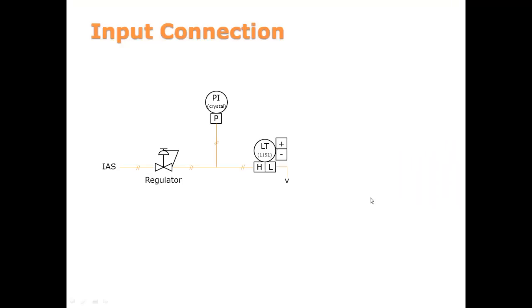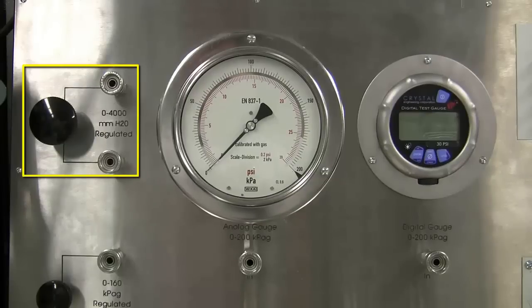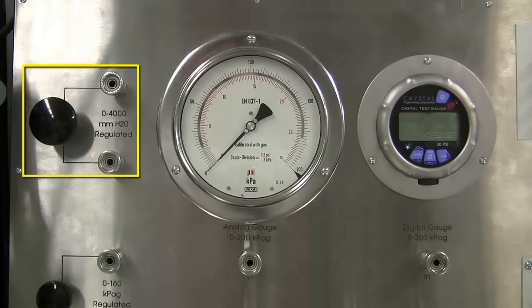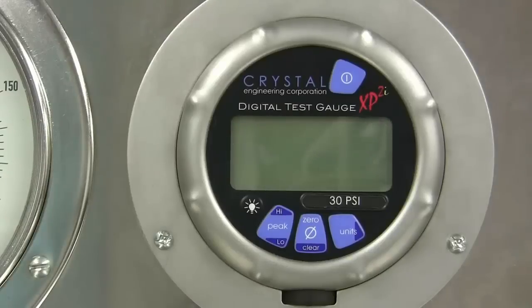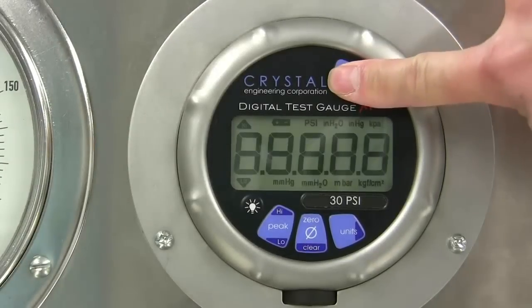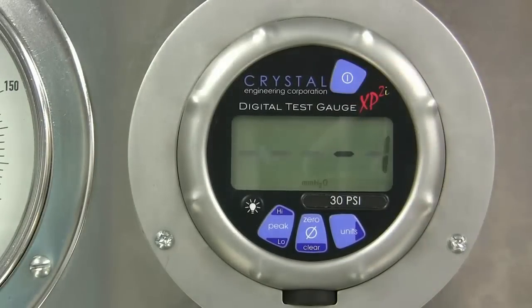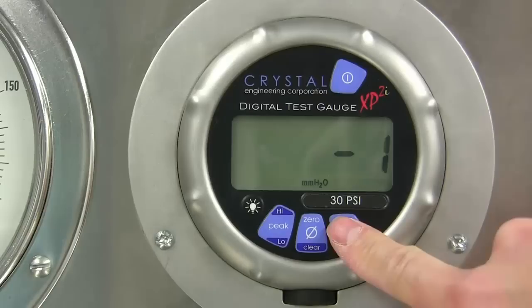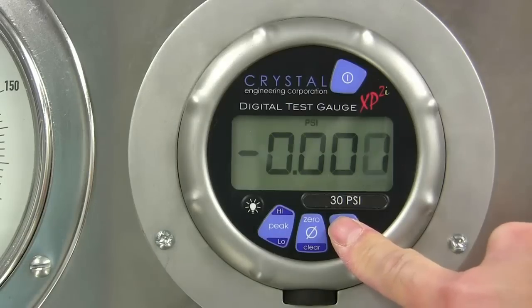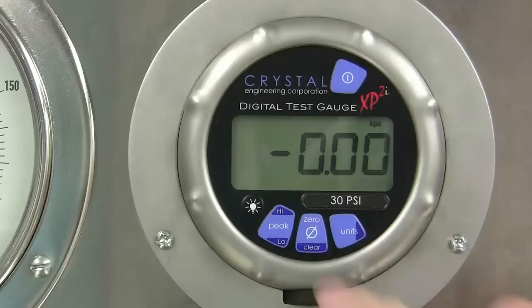We will now connect up the input side of the level transmitter. Recall that the output of the regulator is sent to the level transmitter and the pressure indicator. We will be using the zero to 4,000 millimeter H2O regulator, which has two output ports available. First power on the crystal gauge by holding down the power button. Then change the units to kPa. Then zero the gauge by holding down the zero button until you see a dash line.